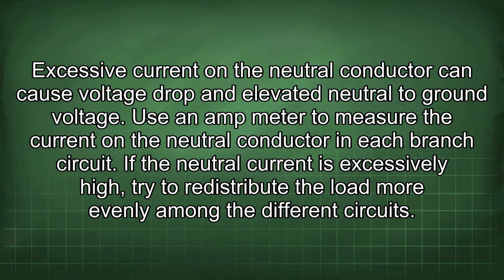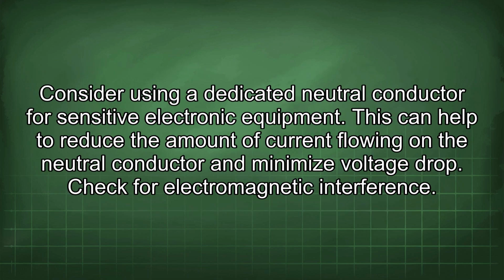Excessive current on the neutral conductor can cause voltage drop and elevated neutral to ground voltage. Use an ammeter to measure the current on the neutral conductor in each branch circuit. If the neutral current is excessively high, try to redistribute the load more evenly among the different circuits. Consider using a dedicated neutral conductor for sensitive electronic equipment. This can help to reduce the amount of current flowing on the neutral conductor and minimize voltage drop.